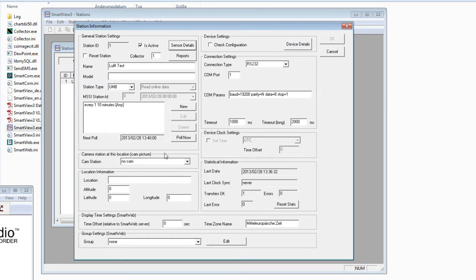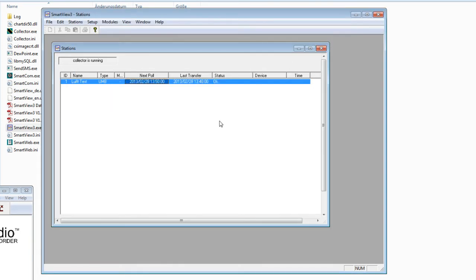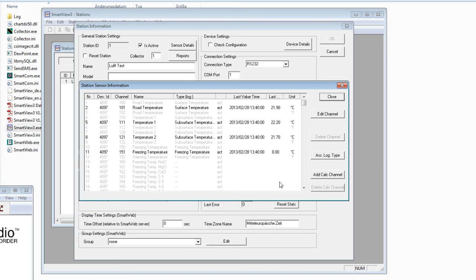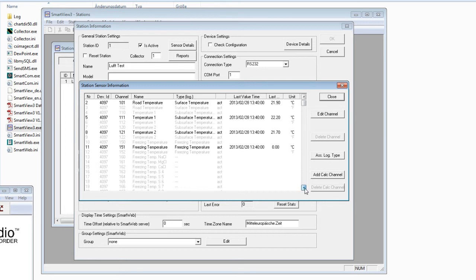For example, for the road sensor we choose the surface temperature — mark it, right mouse click, set active. Now the channel is black, meaning it is active. Choose all the different channels you want for the station. Then click Poll Now and OK. After polling, go back to Sensor Details and you will see actual values now being written into the MySQL database.